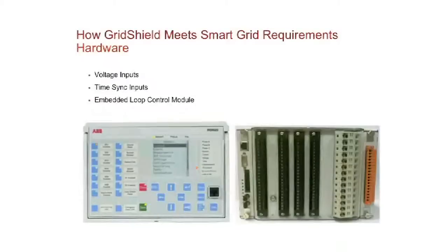So you need to have the hardware that supports that type of application, 6 voltage inputs. You might have applications where you need to use PTs because you need a lot of accuracy, or you have applications where all you need is 1% accuracy, so you can use sensors. So you need a technology that, without adding any additional hardware, allows you to interface with instrument transformers. Or if I don't want to use instrument transformers and I want to use sensors, then this technology, for example the voltage input card, supports any type of voltage sensing equipment, whether it's a PT or a sensor, without adding any additional hardware.